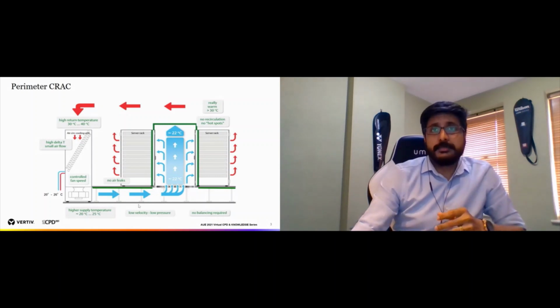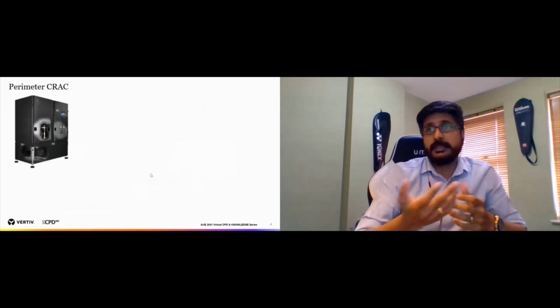Now, CRACs, as initially, which Rob was covering in the slides. Liebert is our company, and around 1965 we were the inventors of the CRAC unit systems, the computer room air conditioning systems. Traditionally, CRACs are DX units, and now we call any chilled water perimeter cooling units CRAH units, or computer room air handling units. Traditionally, they have a DX system where the compressor, evaporator and expansion valve sit inside, and the condenser sits outside. So that's a traditional refrigeration circuit.